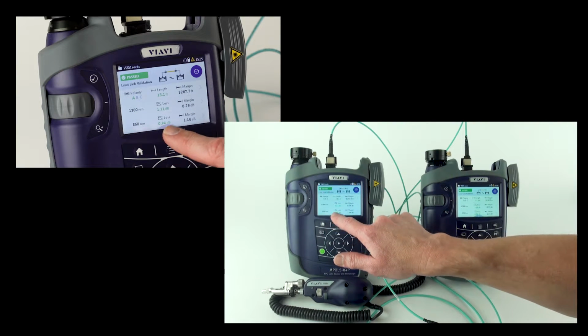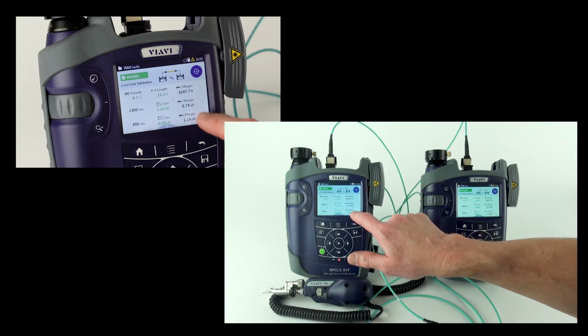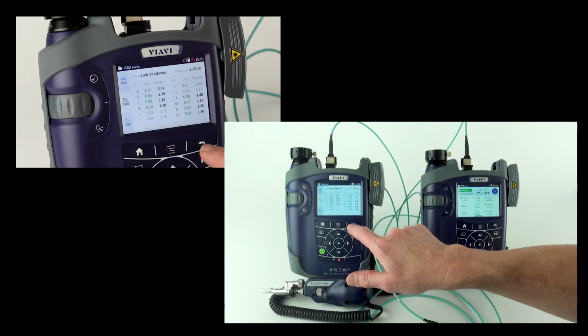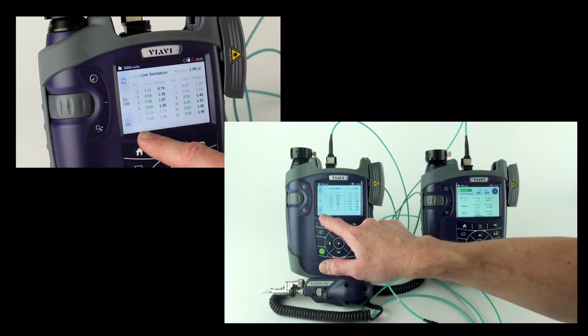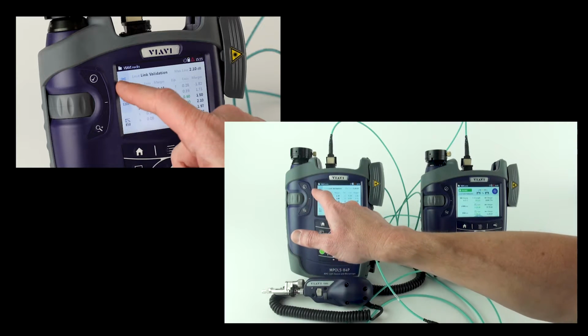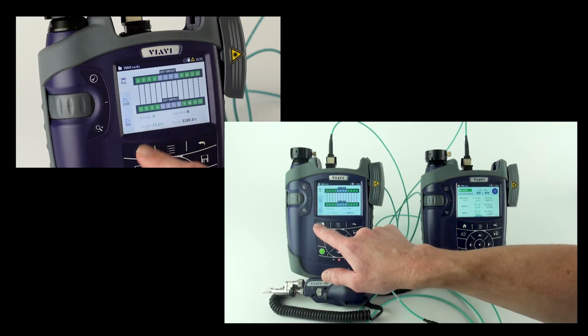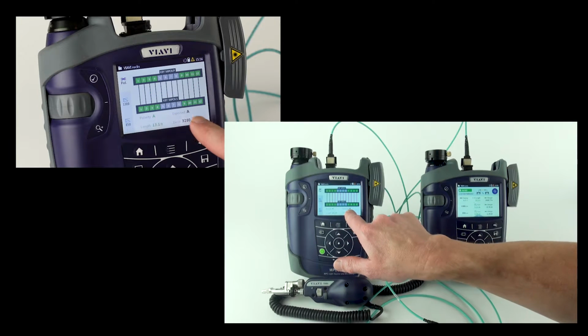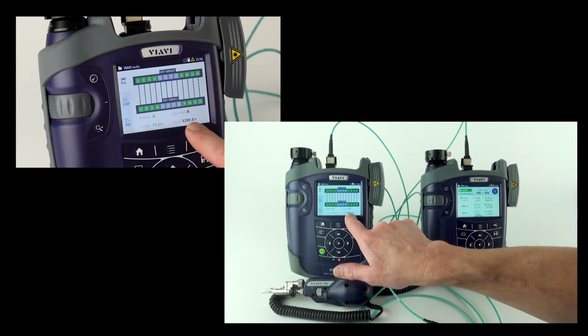I can see my 2 wavelengths, I can see the loss, and I can see the margin, and then I can choose to go into a detailed view. And when I go into a detailed view, I can choose to look at different elements. So if I start at the top, I see polarity, and I see that it's polarity A, it was expected A, the length, and the length limit.